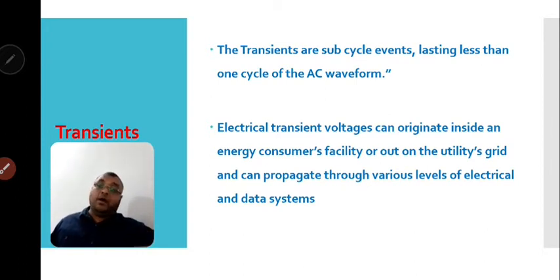For example, if a transient occurs for 4 milliseconds and is characterized by a frequency content of 40 kilohertz, then the measuring instrument must have a frequency response or sampling rate of at least 10 times that, i.e. 400 kilohertz, in order to fairly describe the characteristics of the transient.